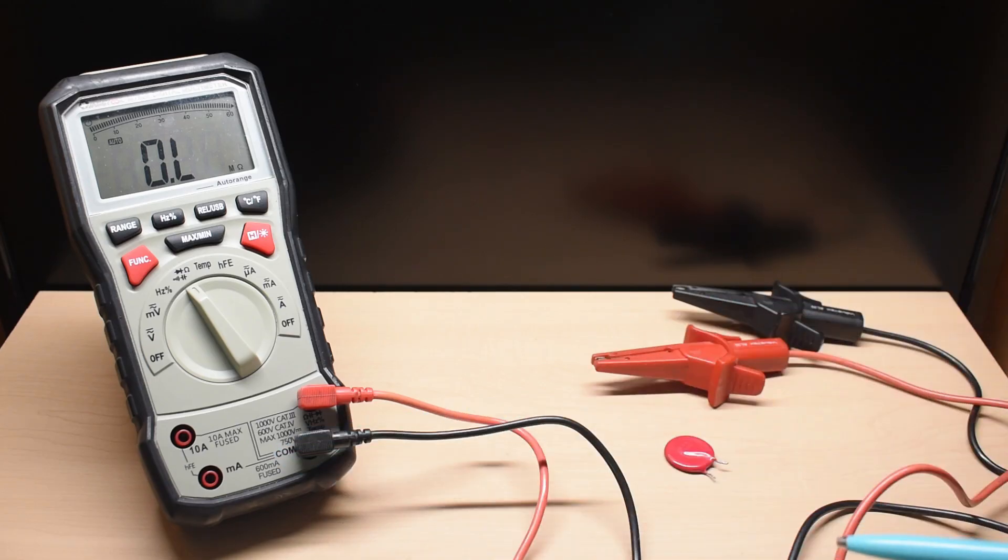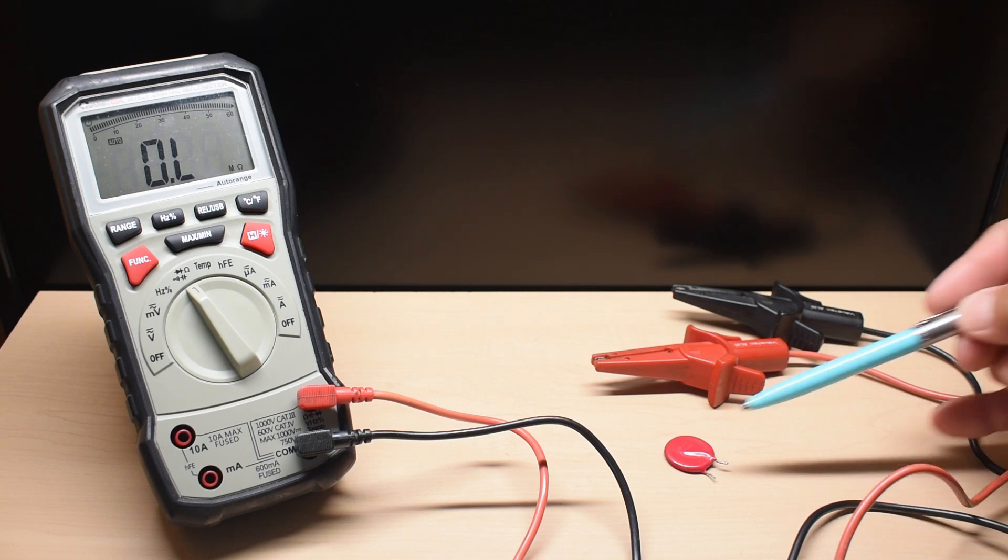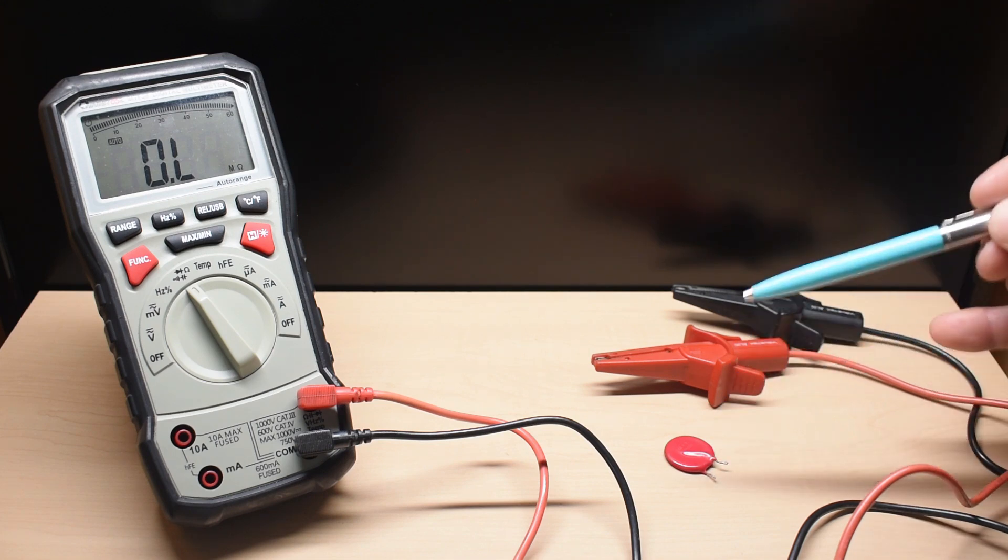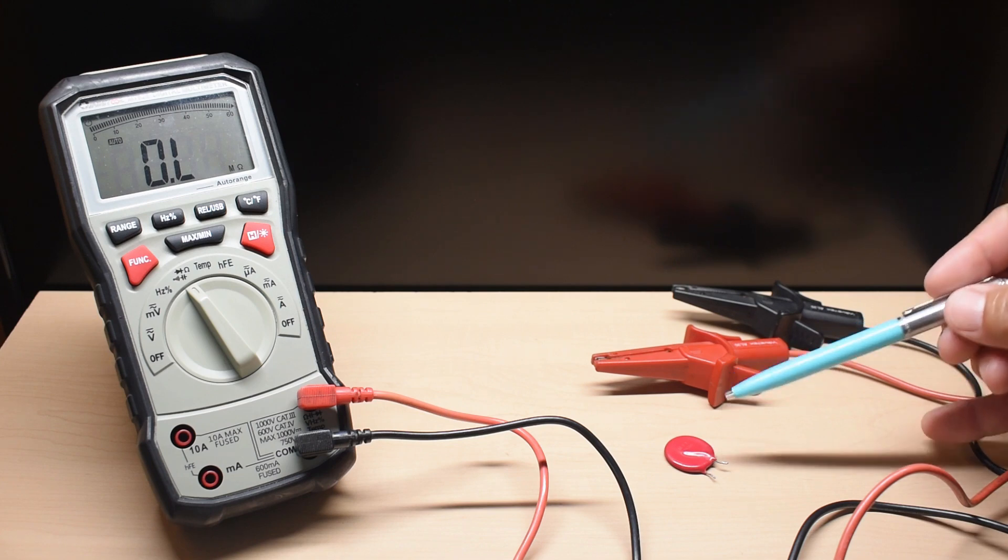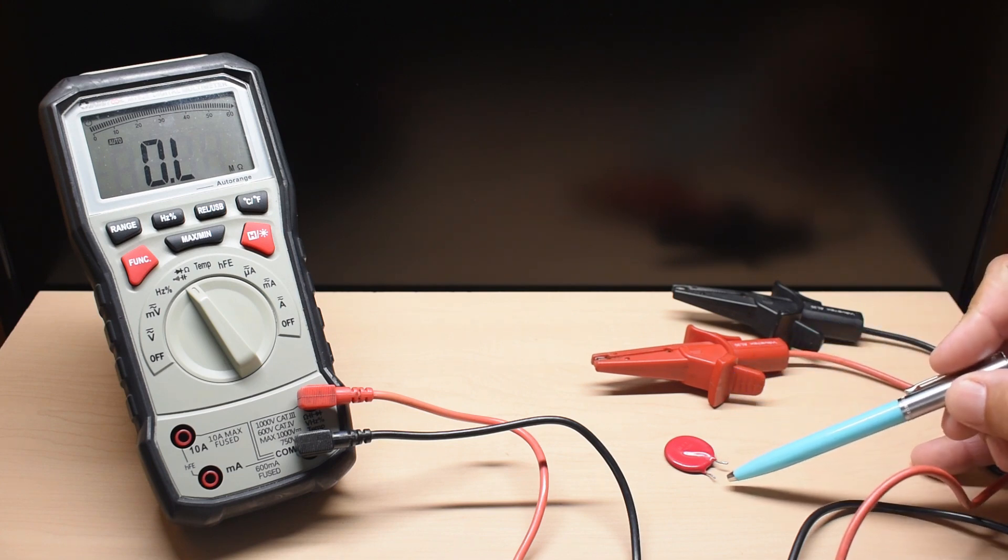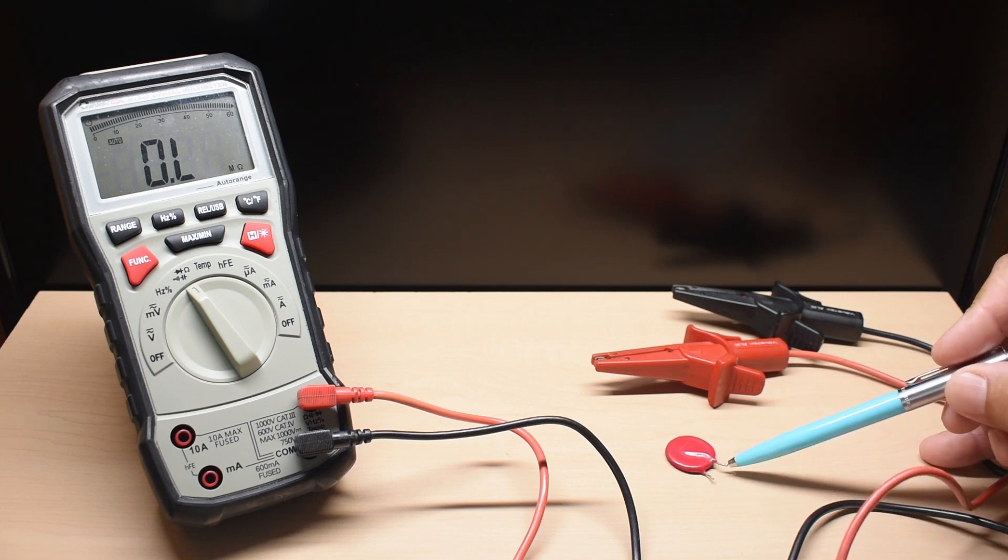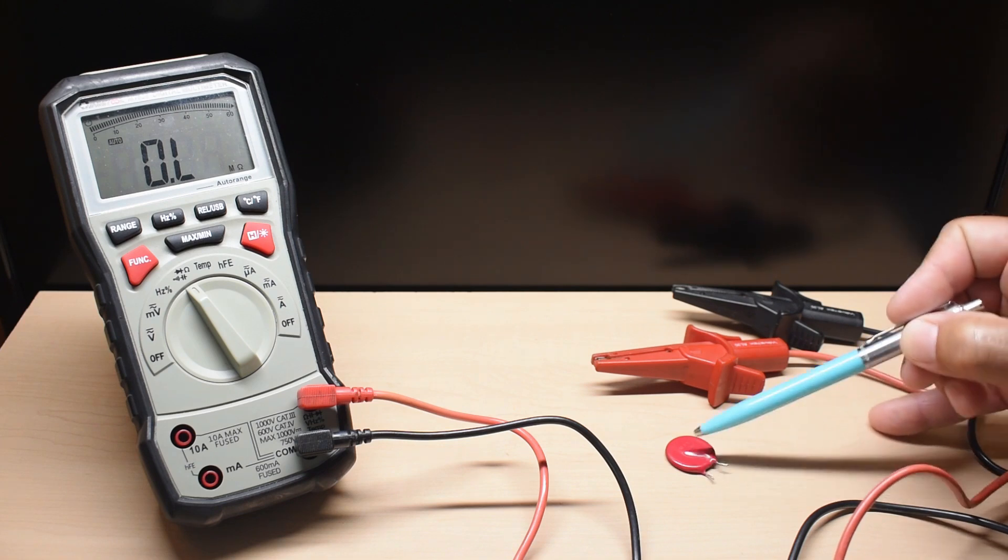Now I'm going to give you a few different demonstrations and it's going to make you understand very easily how this works. So right here we have 150 volts AC maximum voltage rating, like I told you a minute ago. And if it's going to be used with DC, it is 200. So there's other ratings tied to MOVs. The continuous voltage rating is up to 150. And that means as long as you're using up to 150 volts and you do not exceed that, there's going to be no connection between this terminal here and this terminal here. Basically, you have an open circuit right here.